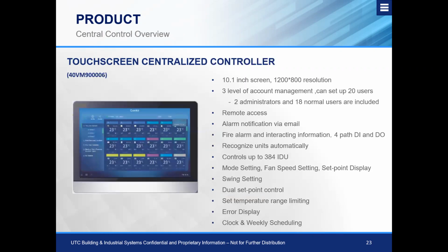If we look at the centralized controller, of course, this is going to be used in central locations for the entire system. So we have 3 different levels of account management, and it's set up for 20 different users with 2 administrators and 18 normal users, depending on the application that we're working with. We also have the ability for remote access. It's set up with an IP address so that you can dial in remotely to the centralized controller if you're not on site.